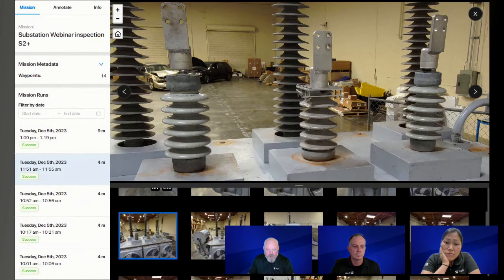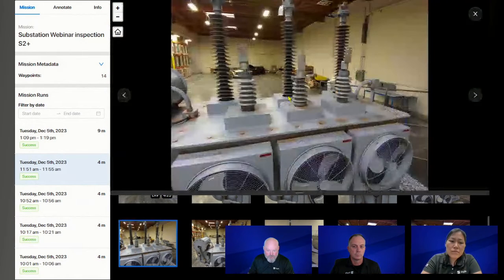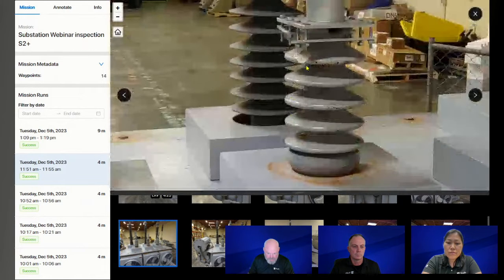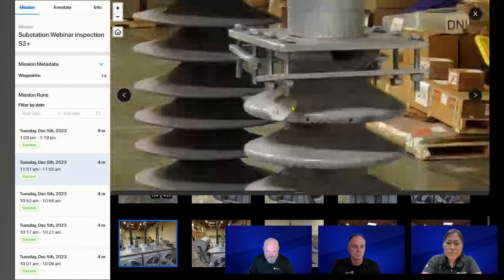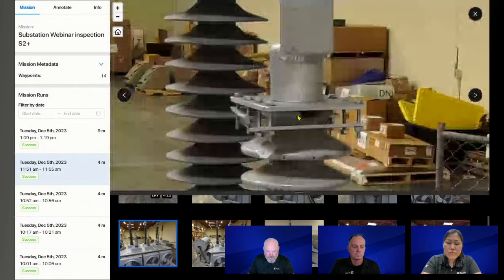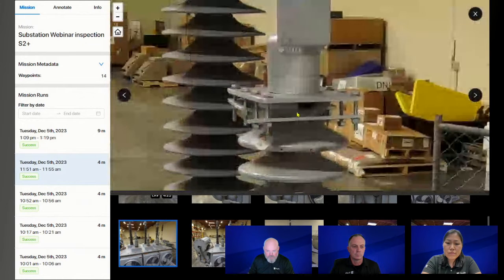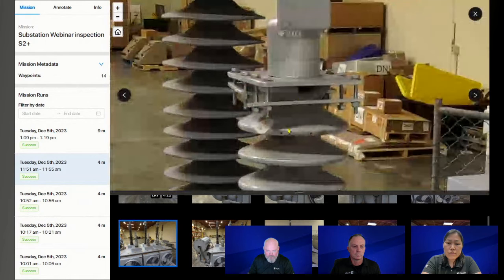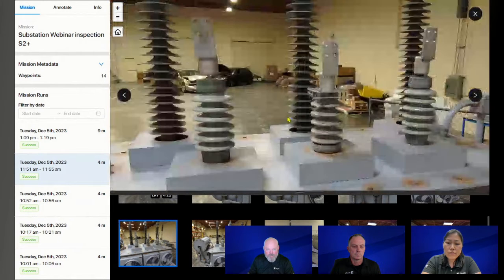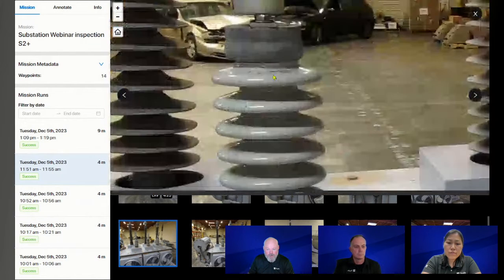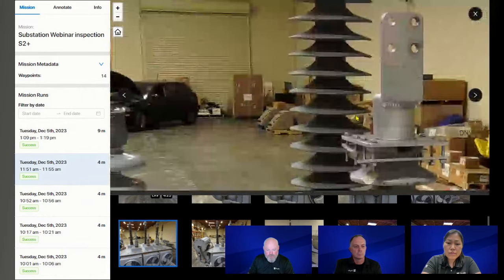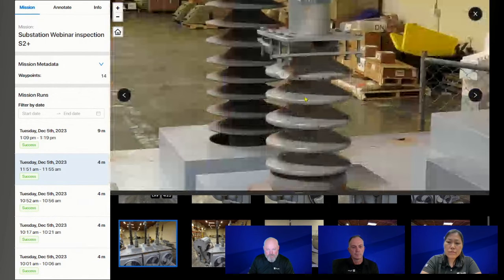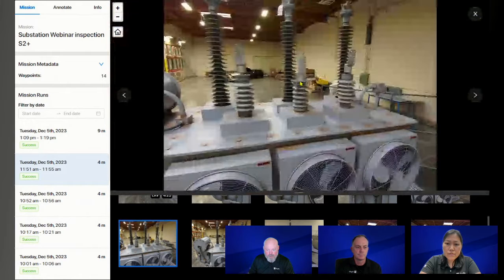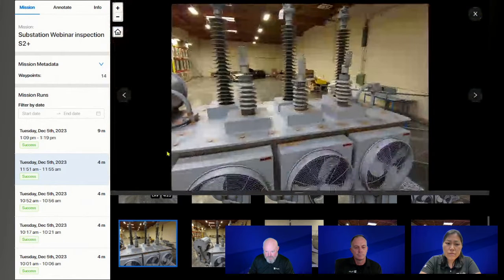But if we look at this low side image we captured during our inspection, we can see that we've got a chipped insulator, and somebody didn't order the right bushing, so there's a whole bunch of weird parts bolted to the top of this thing, as opposed to this bushing, which looks properly installed. So we're probably going to set up a work order for that and send some folks out to have a look and see if they can't make repairs.